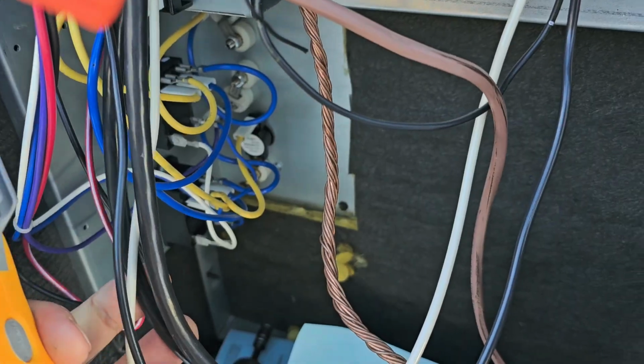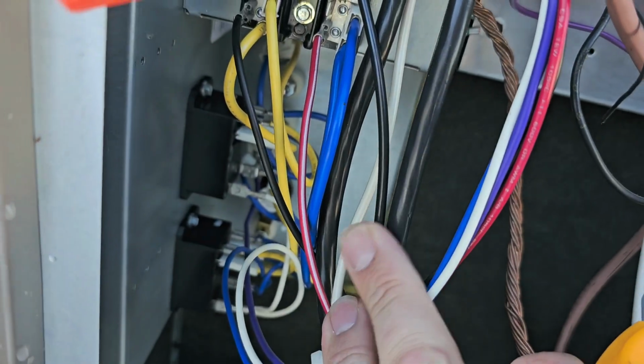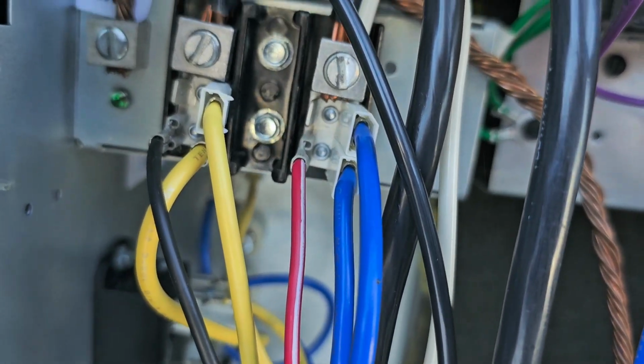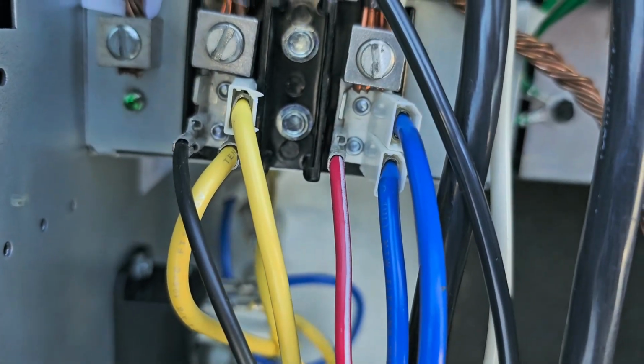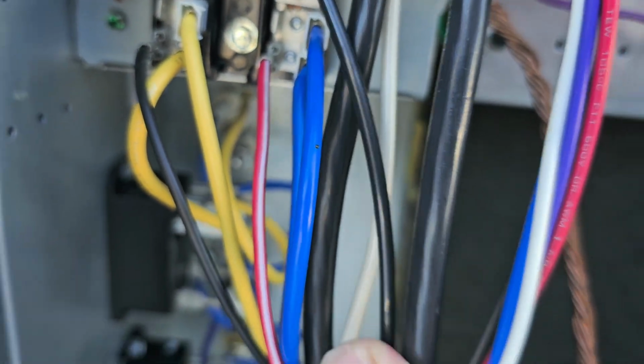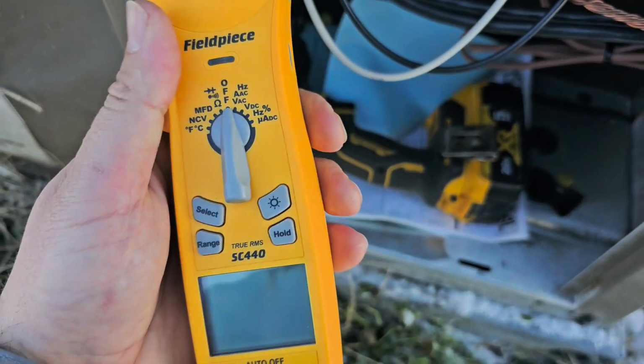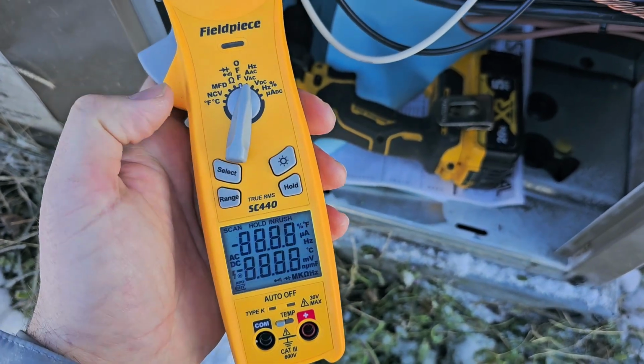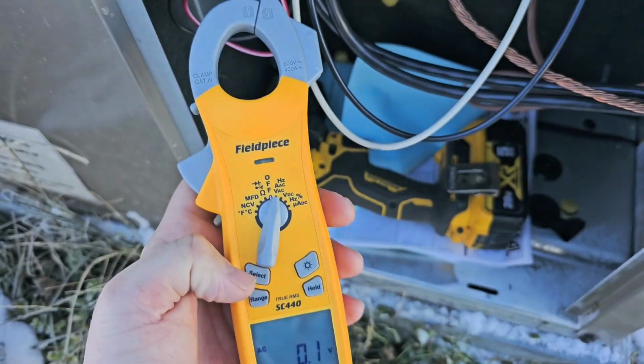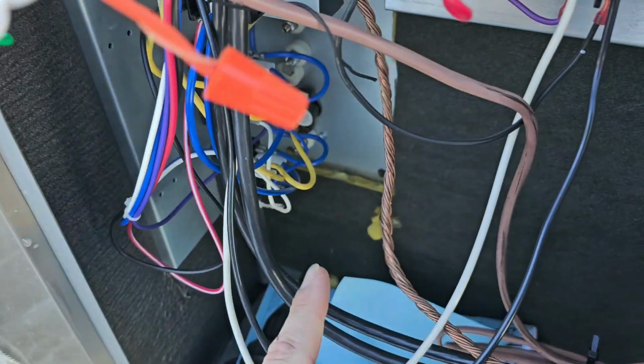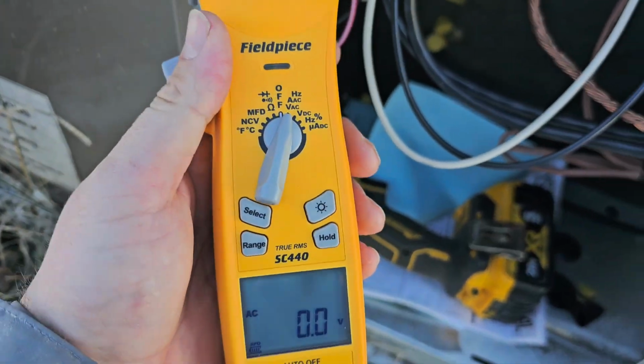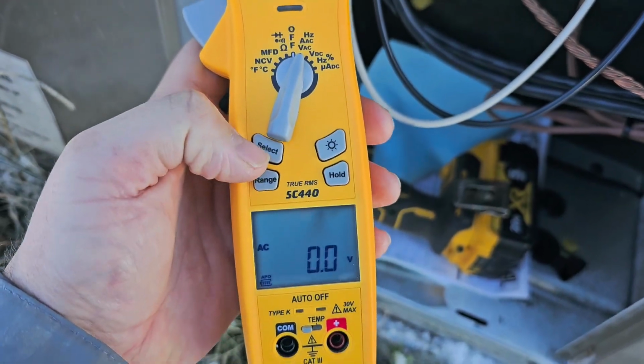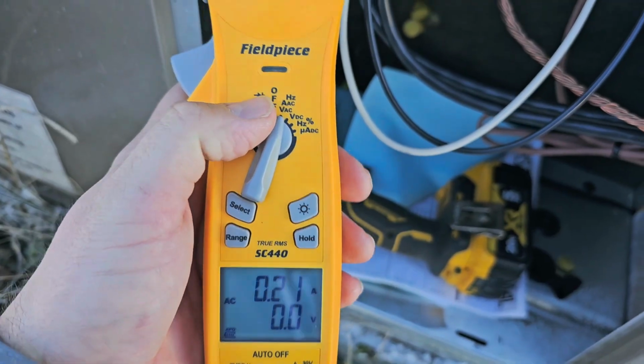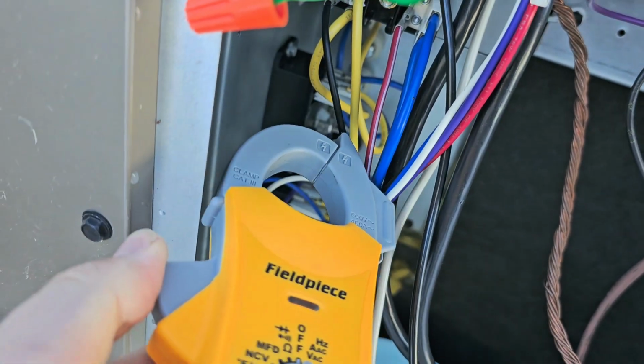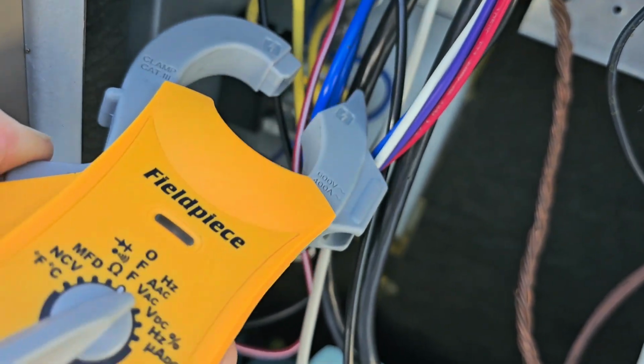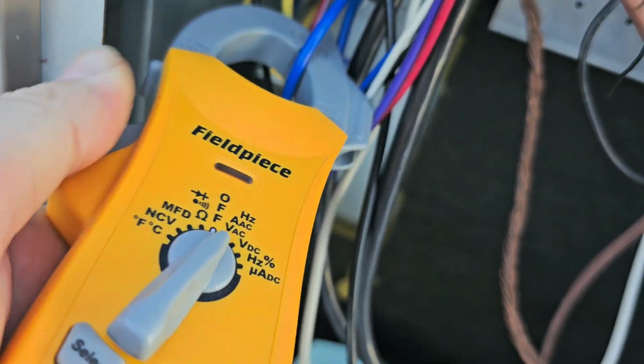Now, I'm going to show you another way to verify if the heater kit is actually working. We've got our power going into the heater kit, and we've got two yellow wires going in, two blue wires going out. And we can use our amp clamp to measure the amperage, right? Because each heater, if this is 10 kW, each heater should be pulling somewhere around 20 amps, right? So we're gonna hit the select button, turn it on AAC, and we are gonna take and put our clamp around each wire.